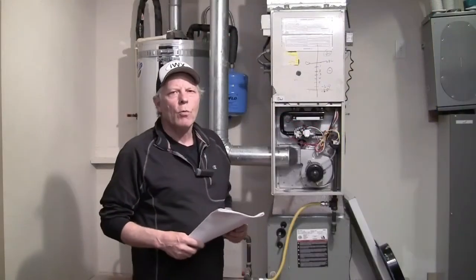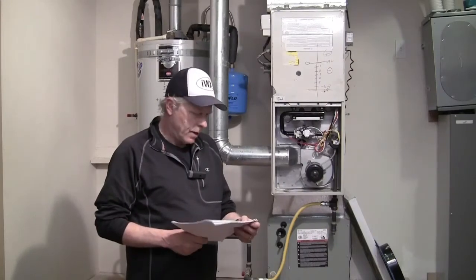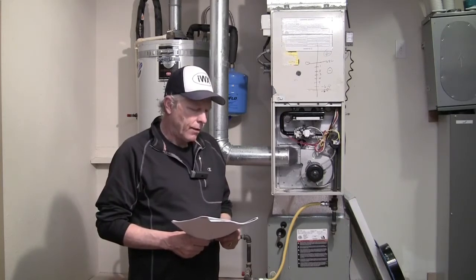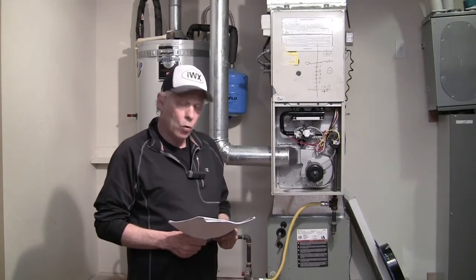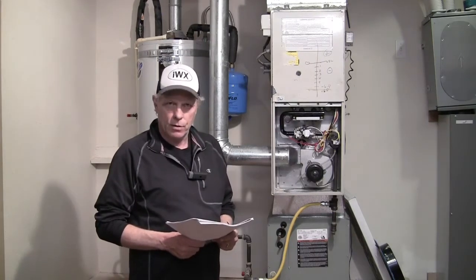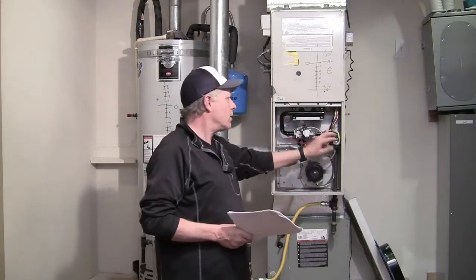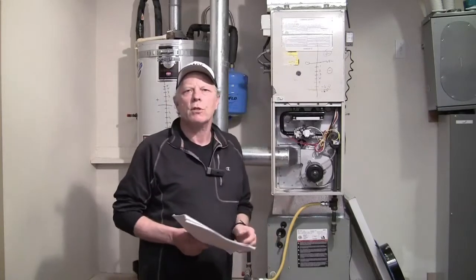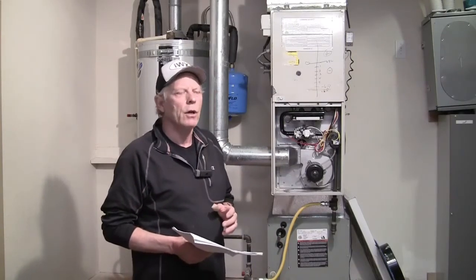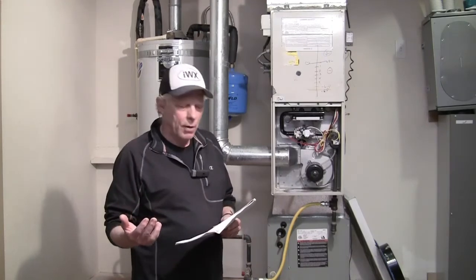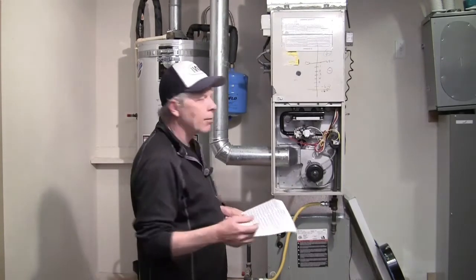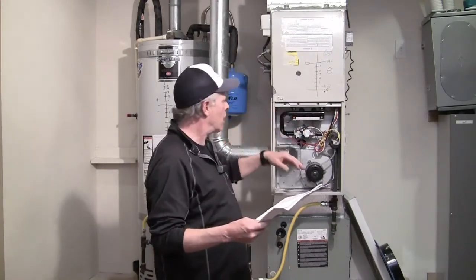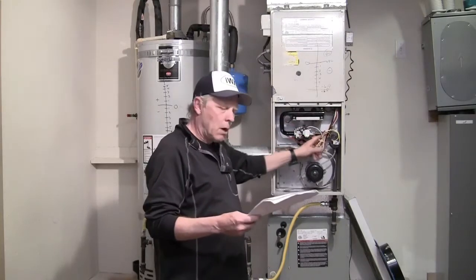Okay, the next line we're going to work on is line 4 of heating, cooling, and domestic hot water equipment. That asks the candidate to identify or discuss existing heating, cooling system health and safety concerns. You know, in most test houses, we're not going to have those types of concerns. So this is something where you're going to have to talk to the proctor about some items that you may have seen in the past. You know, in general, maybe some things like clogged filters could set the high limit off. We could have melted wires in here.